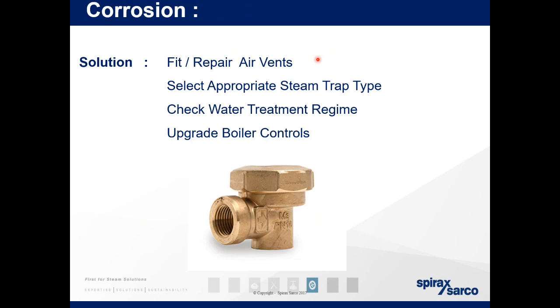What happens is when you're cooling down your steam system, the steam collapses, which pulls a vacuum. What's needed to fill that vacuum is normally air. The steam system will look for the weakest point in your pipework, which usually is the gasket in between flanges, and it will make them leak. It will pull the air in through that gasket, cracking it and causing damage. That means when your steam system then fires up, you've got a leakage path for steam too. So by installing air vents to remove the air, and vacuum breakers to add the air when the system is cooling down, you will prevent the wear and tear of gaskets and leakages.